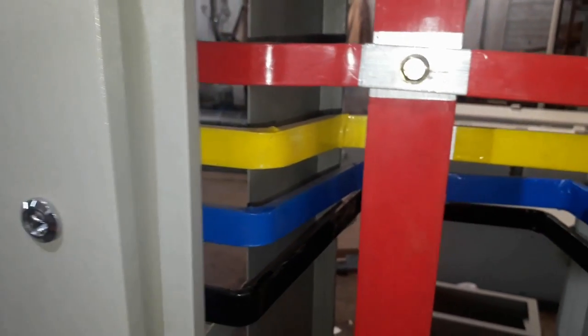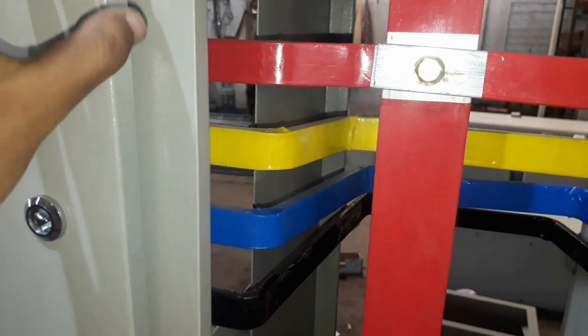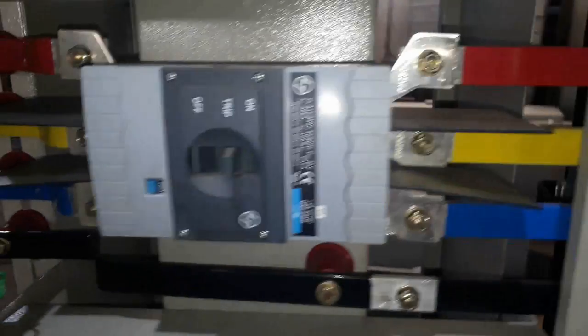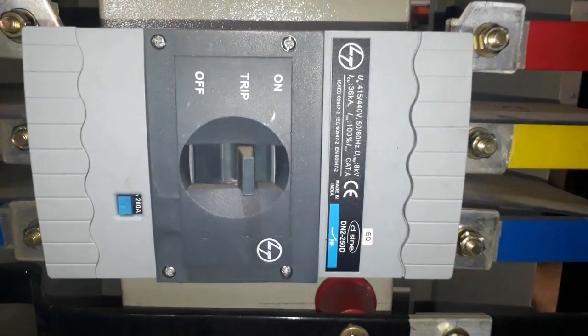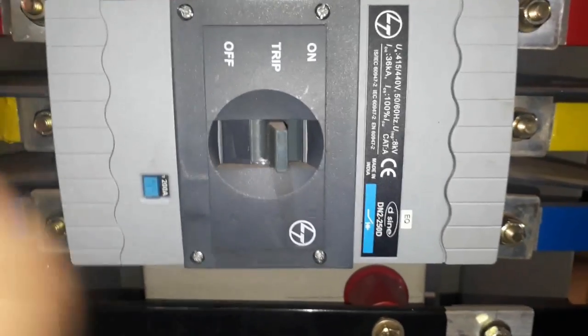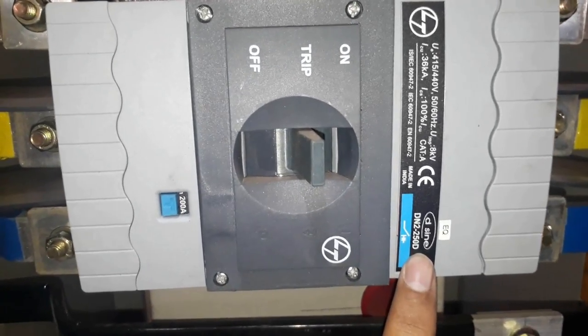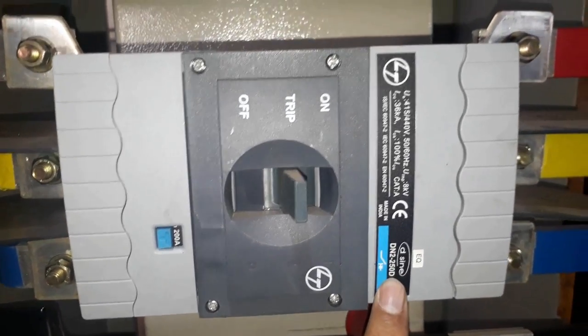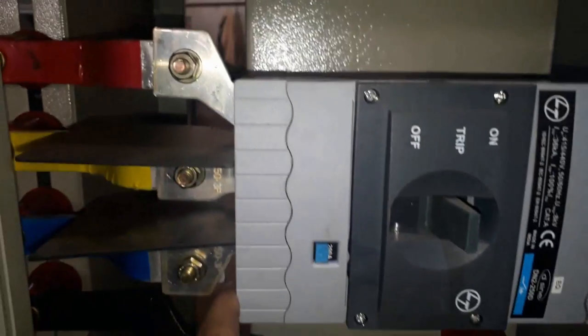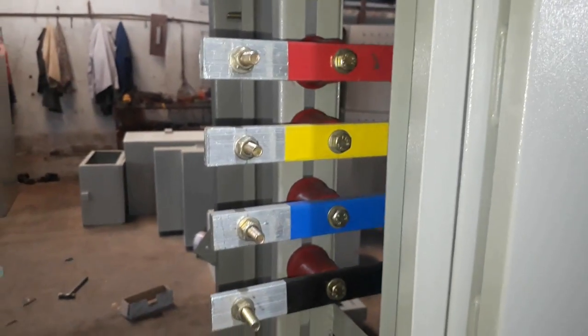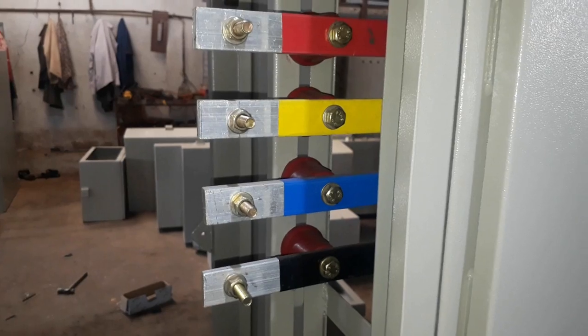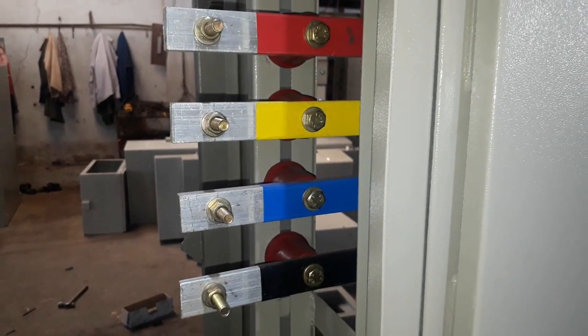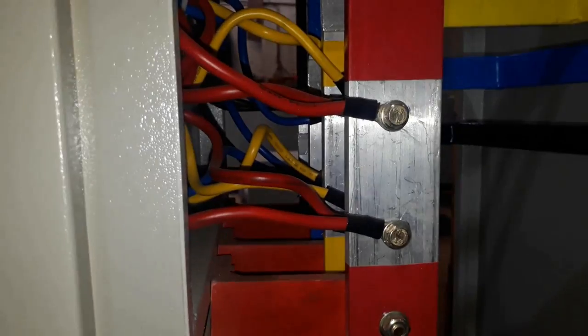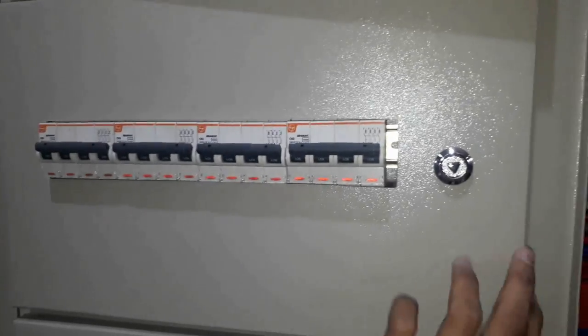Here you can see we have used a bus bar instead of cable to transfer the power to the phase in of the MCCB. This one is a 250 ampere MCCB, and if the ampere rating is above 100 ampere, we have to use bus bars instead of cable. Hence we are using bus bars here for the 250 ampere MCCB. This one is an output chamber or cable chamber, and the load is connected from this chamber. At the bottom of that, there are more circuit breakers located here.